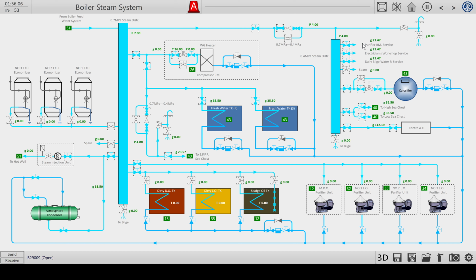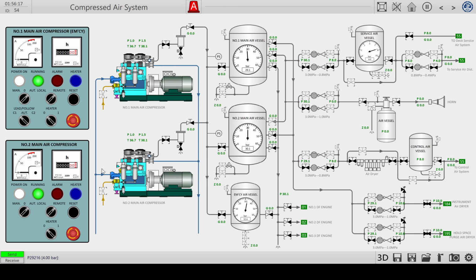Steam is used for all the necessary systems to heat up the water. You see here we don't use any purification, nothing special over here. Air compressors, two main vessels, and the emergency vessel is filled at a normal level. I do see that the two air compressors are in auto mode, but they keep running continuously, and there's an overpressure valve going open, so I'm not sure why this is, but they turn on if we have enough pressure.